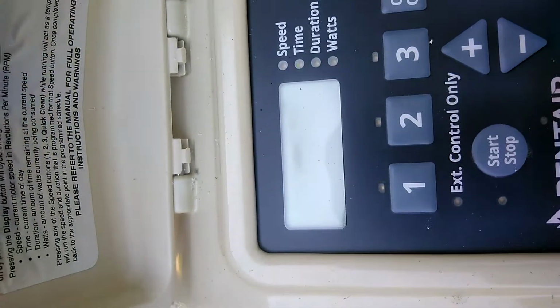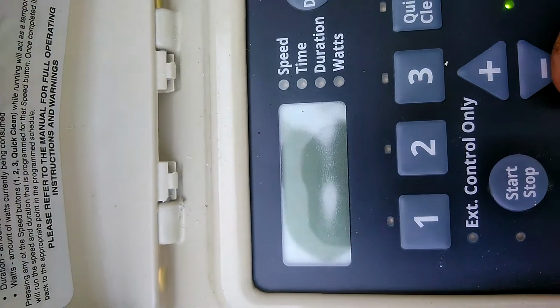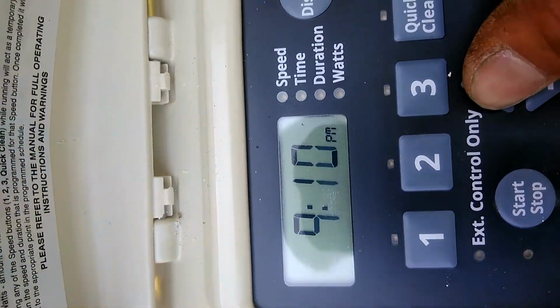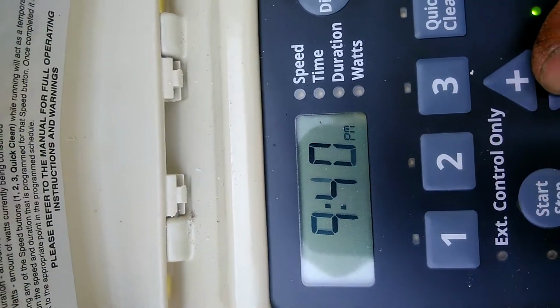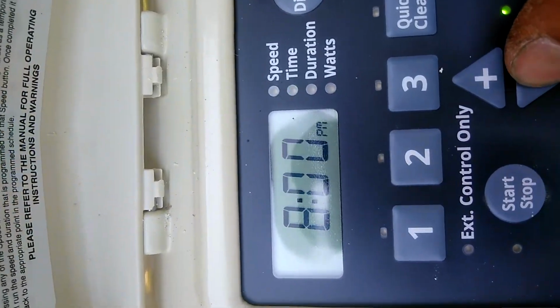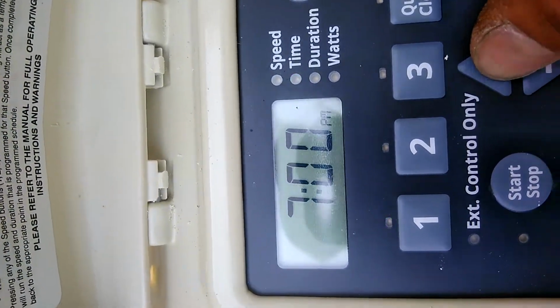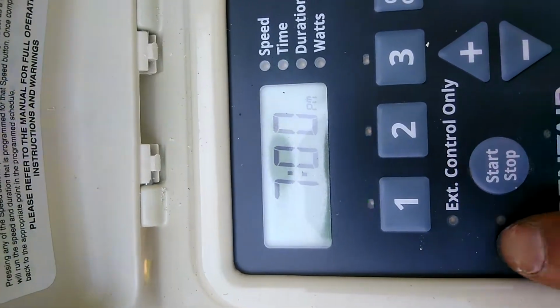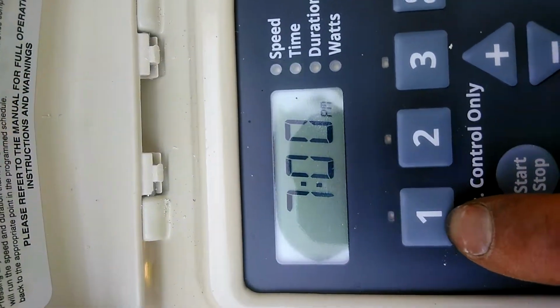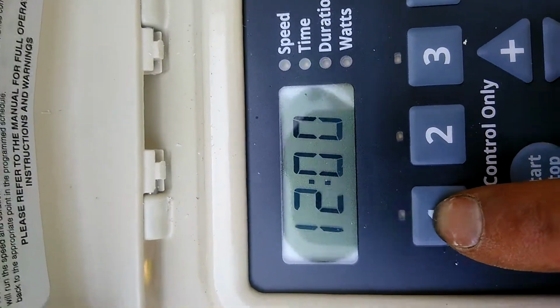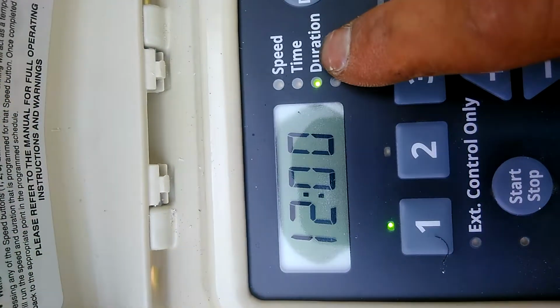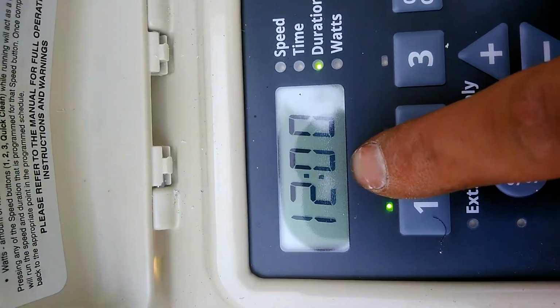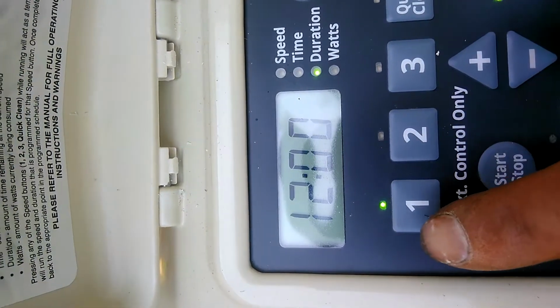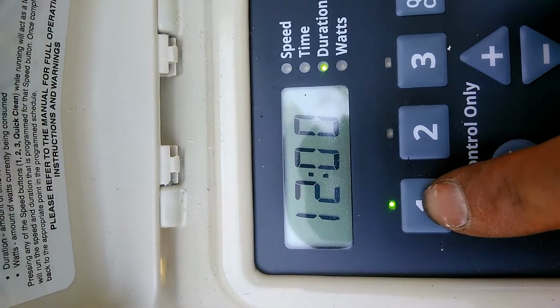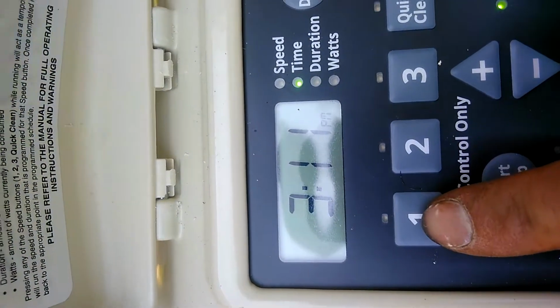Once I hit this again, it's going to ask me, when do you want me to start speed 1? Okay, so in this particular case, I'm going to start this at 7 p.m. What I'm going to do here is 12 hours at nighttime because that's generally when hydro's cheaper. Okay, so I'm at 7 p.m. start time. I'm going to hit the 1 button again. Now it's asking me duration. So how long do I want to run this for? So I'll say 12 hours. So that'll bring me from 7 p.m. to 7 a.m. on speed number 1, which is 2,000 RPMs.